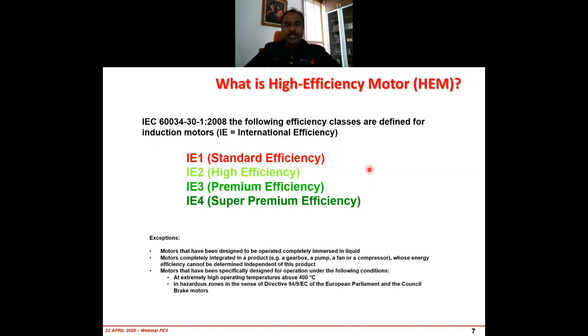So the IE1 motor is a standard efficiency. That means the motor that you have in industry now, we will actually put under the category of standard efficiency. This is not a high efficiency motor, but a standard efficiency motor, IE1. Now, when you say high efficiency motor, it starts from IE2, IE3, IE4. Obviously, when they have three options here, the efficiency of, for example, IE3 is going to be larger than IE2. IE4, the efficiency is going to be larger than IE3.